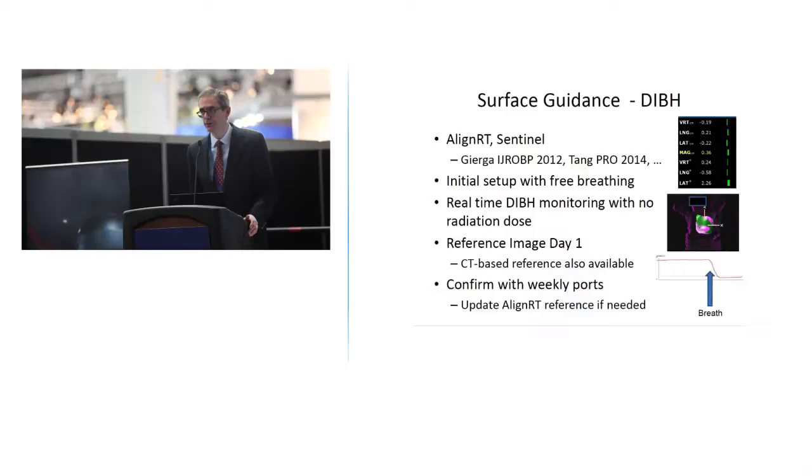Here is the patient's surface under normal respiration. They're asked to take a breath, patient surface moves obviously. We can look at the residual displacements and then decide either manually or automatically to turn the beam on. We generate our reference images on the first day of treatment, but you can also send over information from the CT and create a reference surface in that way. What we do, and probably other places do as well, is we still take port films on a weekly basis and use these as the gold standard for the final treatment position. If we have to update the AlignRT information during the course of the treatment then we'll do so.